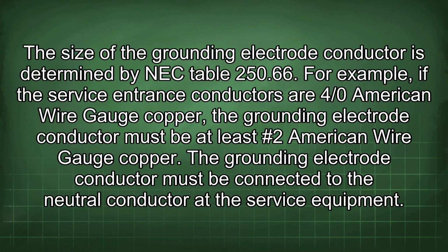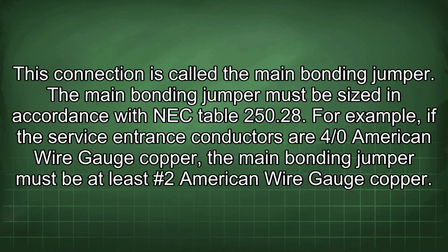The size of the grounding electrode conductor is determined by NEC Table 250.66. For example, if the service entrance conductors are 4/0 American wire gauge copper, the grounding electrode conductor must be at least #2 American wire gauge copper. The grounding electrode conductor must be connected to the neutral conductor at the service equipment. This connection is called the main bonding jumper. The main bonding jumper must be sized in accordance with NEC Table 250.28. For example, if the service entrance conductors are 4/0 American wire gauge copper, the main bonding jumper must be at least #2 American wire gauge copper.